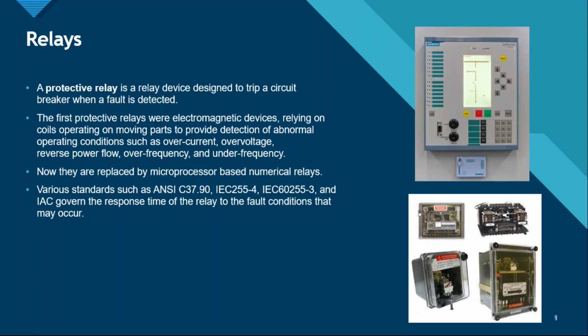The relay, a protective relay, is a relay device designed to trip a circuit breaker when a fault is detected. Different relays have different functions. They can detect different types of faults. Usually, a standard relay can be used to detect any overcurrent fault, if there is an overcurrent happening in the circuit, or an earth current, if there is too much overcurrent happening in the earth circuit. That can be detected by the relay, and it will automatically give a tripping command to the circuit breaker for the circuit breaker to trip open.